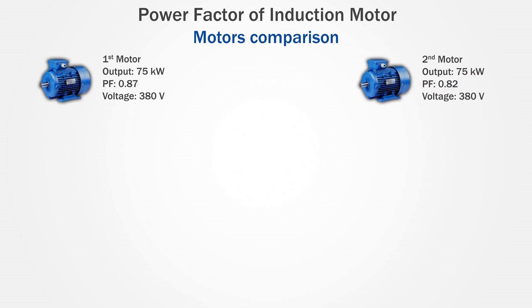Now let's take a look at a comparison between two induction motors. Both have an output of 75 kW and are connected to a three-phase 380V power supply system. The first motor has a power factor of 0.87 and the second one has a power factor of 0.82. We are going to find out how much power each motor will need to draw from the power supply system to provide 75 kW of power. In order to find that out, we need to calculate the apparent power using the power factor formula.